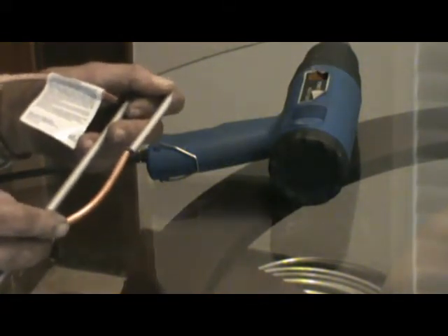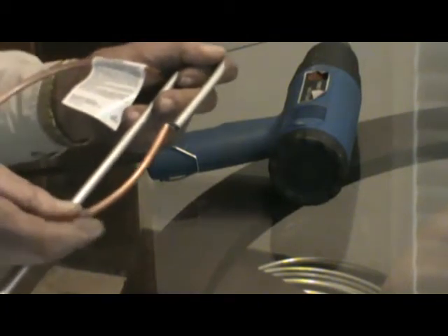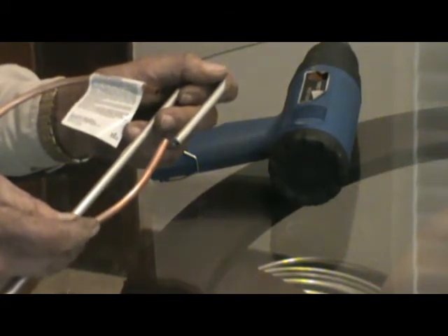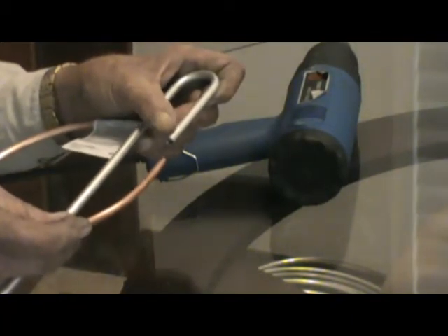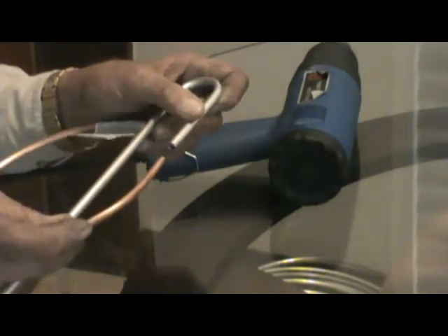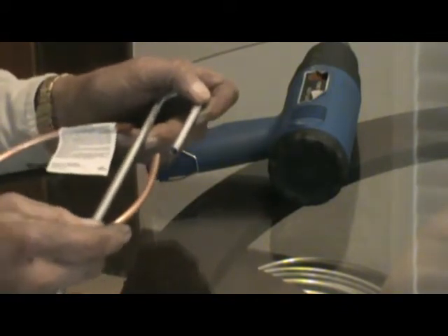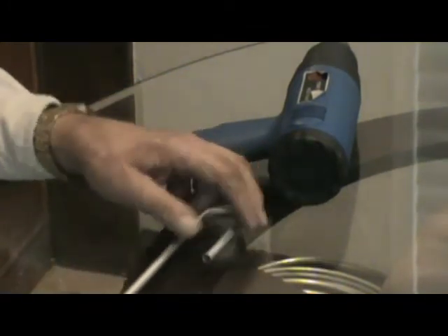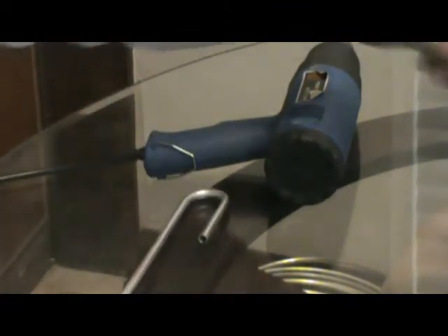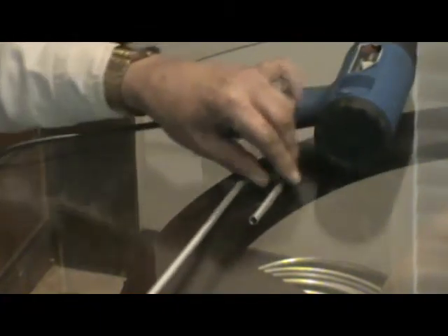Usually about 6 inches, so that there's plenty of room between the solder joint from the heat exchanger, which is going to be down here, and the torch being on it, so it can absorb some of that heat and not melt this aluminum weld. But if you stay on there too long and you have a wrong torch, you're still going to melt this, just like on any evaporator. You don't want to have a wrong torch and too much heat.